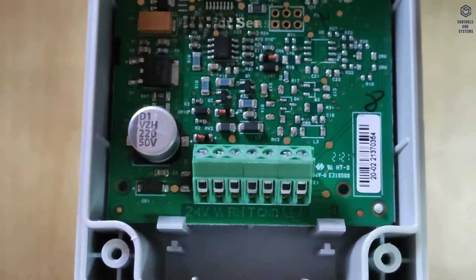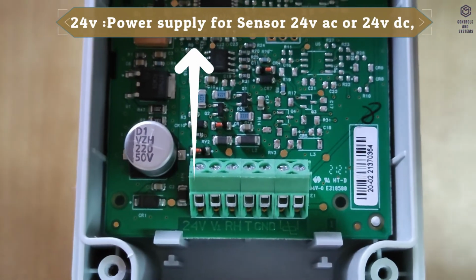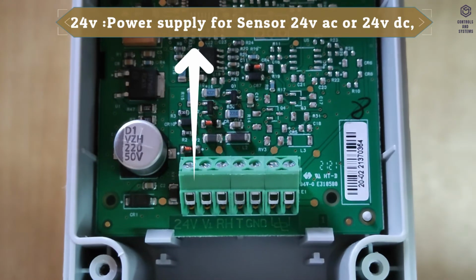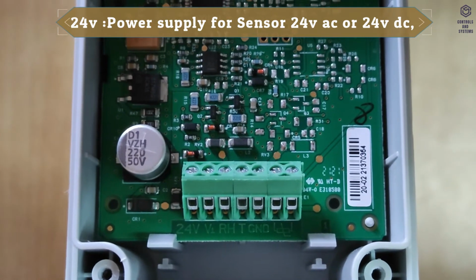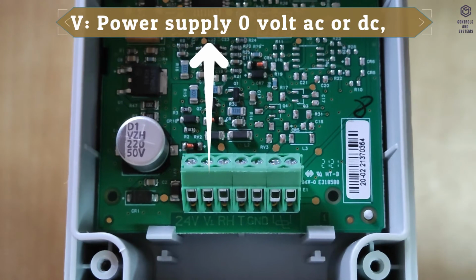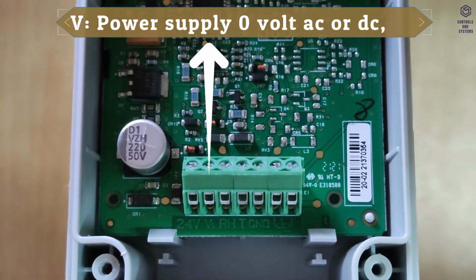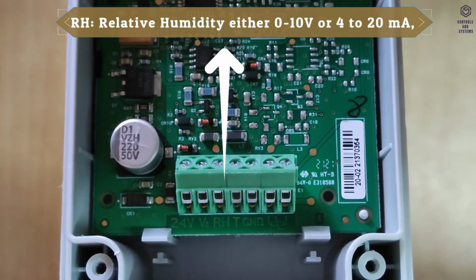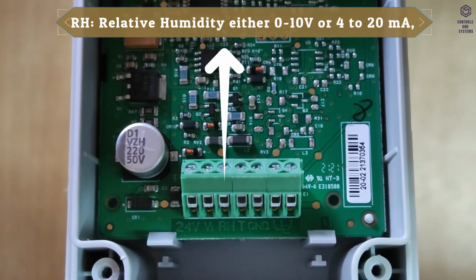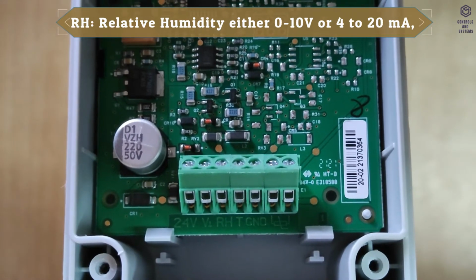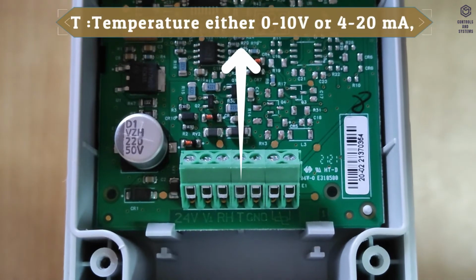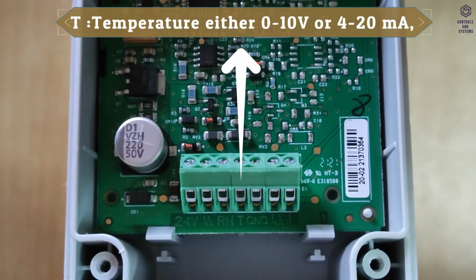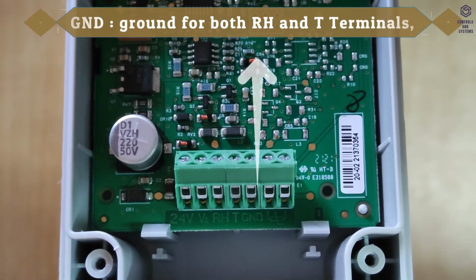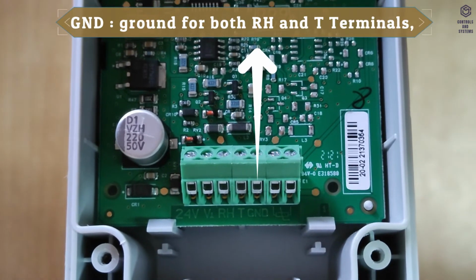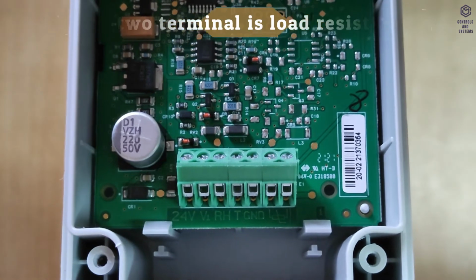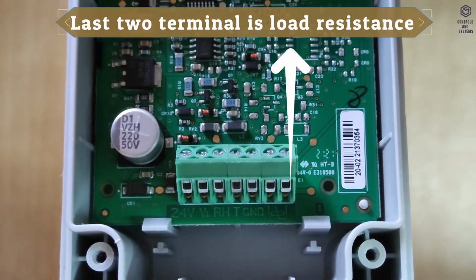Connector terminals. 24V terminal means power supply for the sensor, either 24V AC or 24V DC. 0V terminal means power supply 0V AC or DC. RH terminal means relative humidity, either 0 to 10 volt or 4 to 20 milliamps. T terminal means temperature, either 0 to 10 volt or 4 to 20 milliamps. GND terminal means ground for both humidity and temperature terminals. The last two terminals are for load resistance.